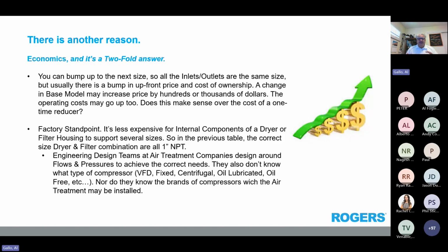The second part of it, because like I said, this is a twofold answer, is the factory standpoint. We can build filters, like I have a little one in my hand, and we can have heads and filter bowls that can handle 3 or 4 sizes. The elements may change inside based on the flow and pressure ratings. So just keep that in mind, that we only have to stock 1 head instead of stocking 3 or 4 or 5 heads for 4 or 5 different flows and sizes and so forth. So that's the other one to think about.